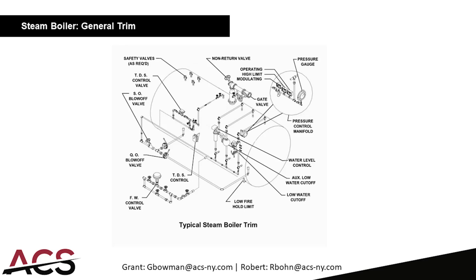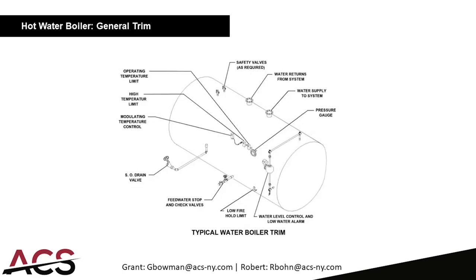This slide covers the hot water boiler general trim. On a high-temperature hot water boiler you have your operating temperature limit, high temperature limit, and a modulating temperature control which modulates the firing rate of the burner. The operating temperature limit determines whether the boiler turns on or off. You also have a slow-opening drain valve, feed water stop and check valves entering the boiler, safety valves as required, water return from your system, water supply going out to your system, and a float-type water level control and water alarm.